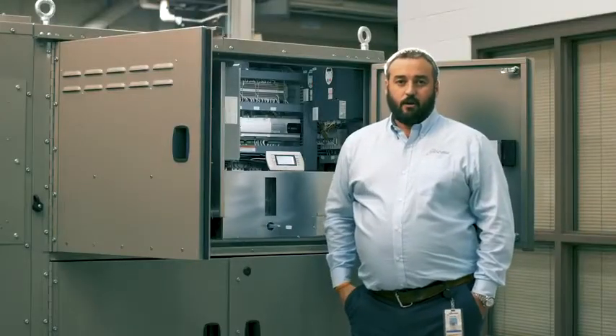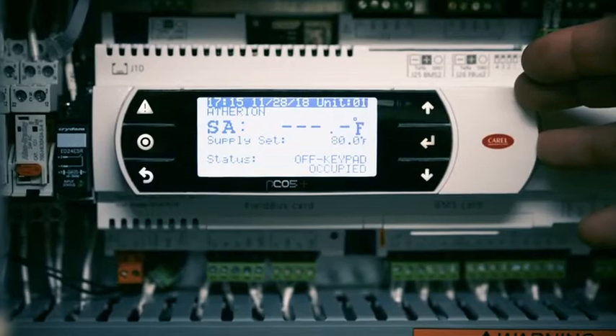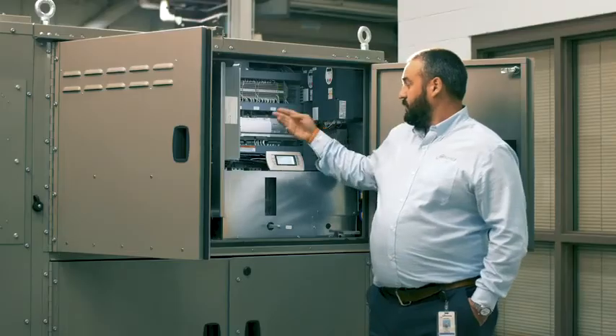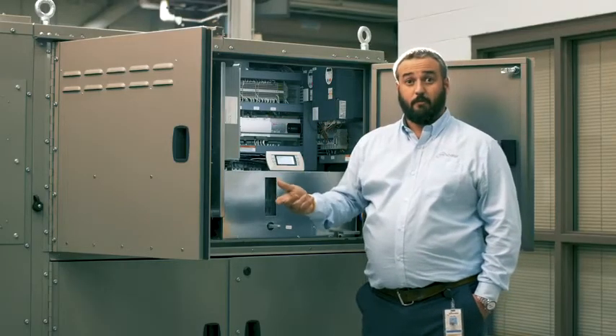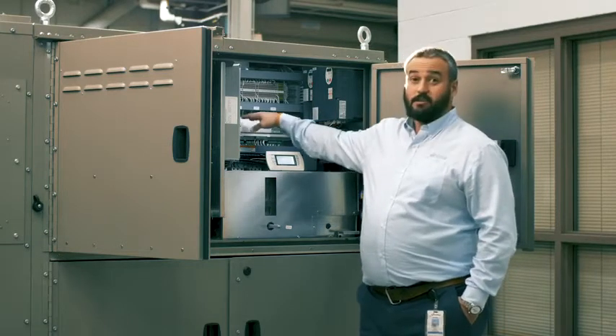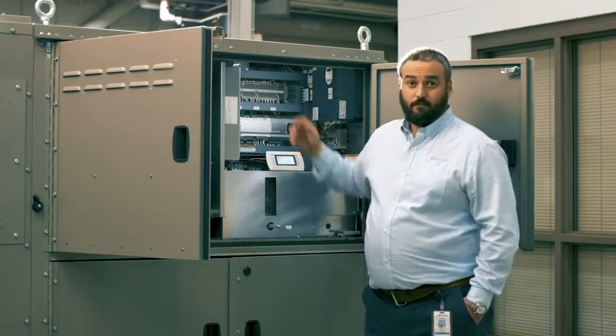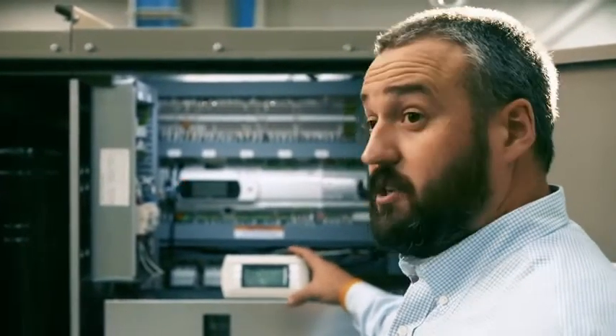So each Atherion comes with a built-in display, which means that the customer can scroll through and see all of the values that we were talking about over the BMS. He can see them in real time standing in front of the unit as well. Not only do you get the built-in display, but you also have an option for a remote display. The good thing about the remote display is it can be fitted anywhere from 0 to 600 feet away from the unit, which means you can install it in a maintenance room or something like that, which gives the customer the opportunity to interface with the unit without going up onto the roof.